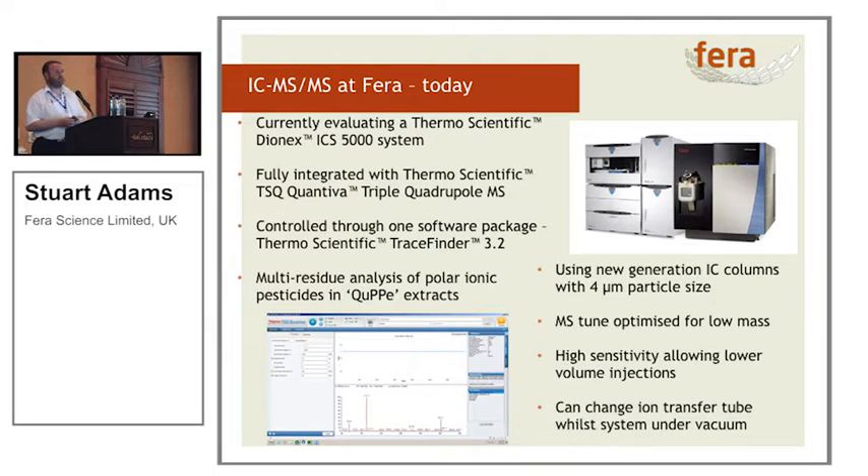So what does IC-MS look like at Fera today? We're evaluating the Thermo ICS5000 system connected to a Thermo Quantiva, and we've got one control software package. When I started, there were two control software packages that never talked to each other. We're heading towards multi-residue analysis. IC is starting to catch up with some of the UPLC developments — we've got a new generation of IC columns with a much smaller particle size. The mass spectrometer is optimised for low mass transitions, giving us higher sensitivity, which means we can drop the injection volume.